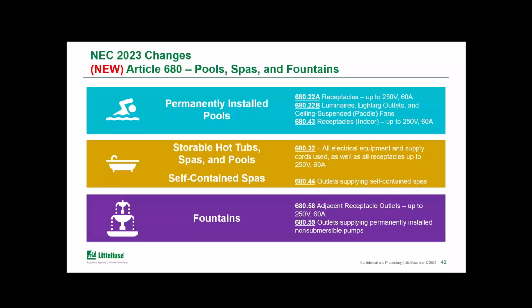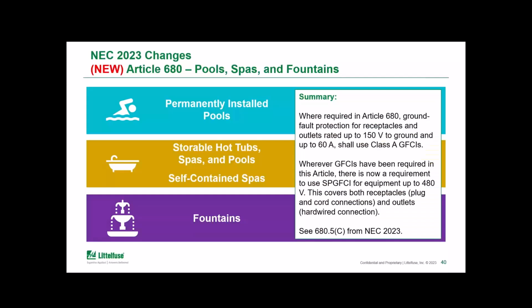Some of the specific clauses are shown here on the screen, but this includes receptacles near permanently installed pools, both indoor and outdoor, electrical equipment used with the storable and portable spas and pools, outlets supplying self-contained spas, receptacles near fountains, and outlets supplying non-submersible pumps. So at the end of the day, the summary is, wherever those Class A GFCIs were used, in general, if there's equipment that now goes above that 150 volts line to ground, up to a maximum of 480, then a Class C special purpose GFCI would need to be used on that higher voltage equipment.